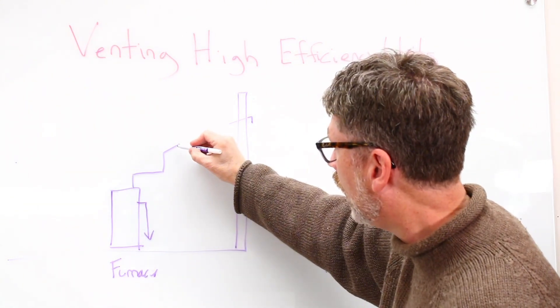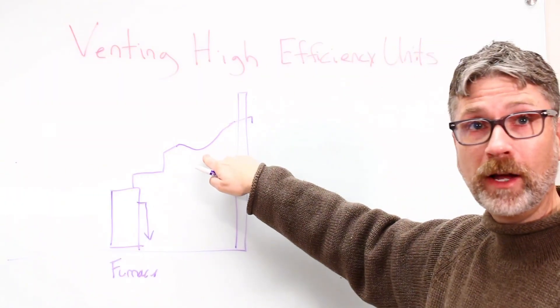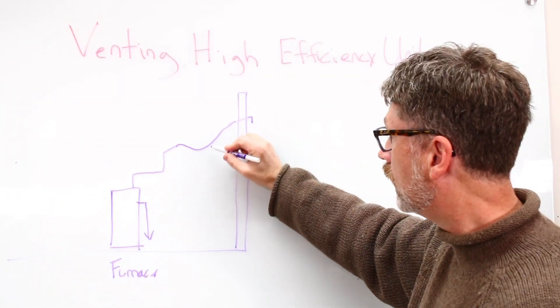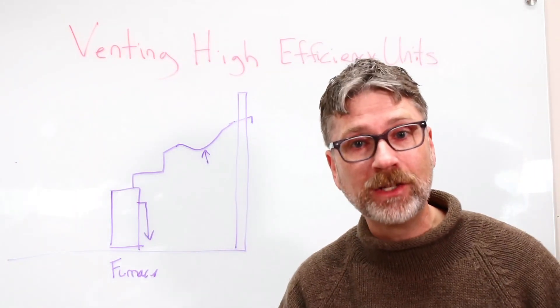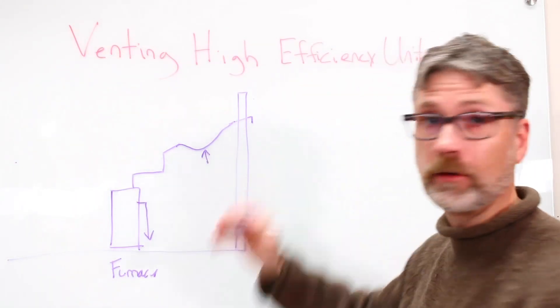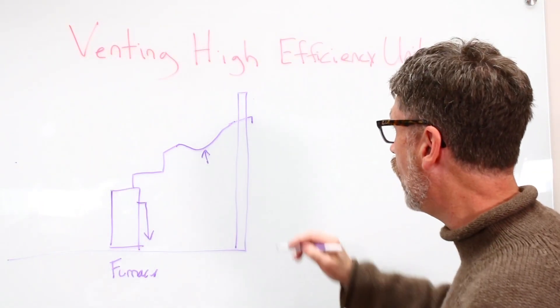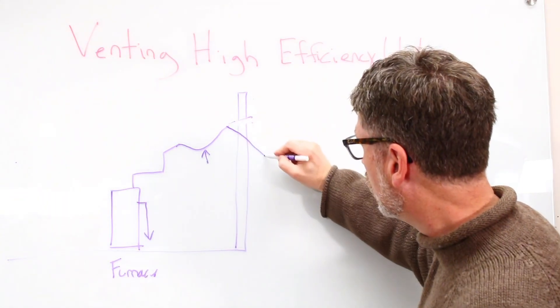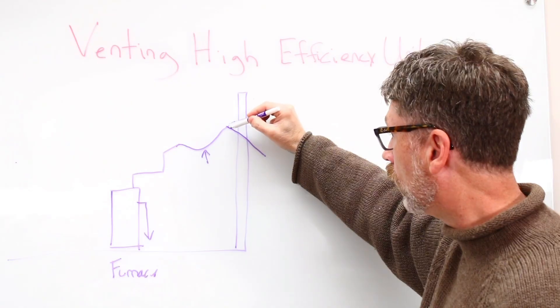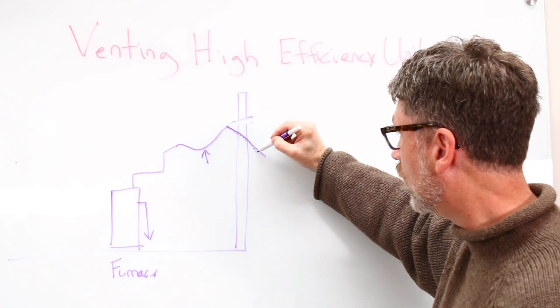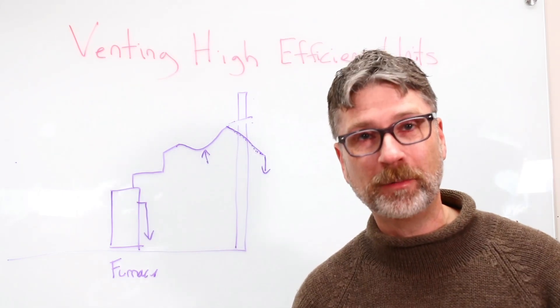If, on the other hand, something happened, it was installed wrong, and you have a sag in your pipe, guess where the water is going to end up? It will pool right here and the unit will sense a blockage in the pipe because it can't push air through the water puddle and it will turn it off. In the same way, you also don't want your pipe to go like this outside because water will form here and dribble down the outside of that and then end up freezing on the outside of your pipe. That will also block your pipe.